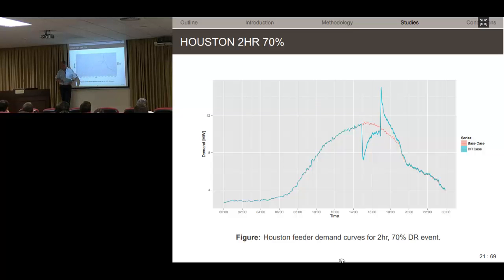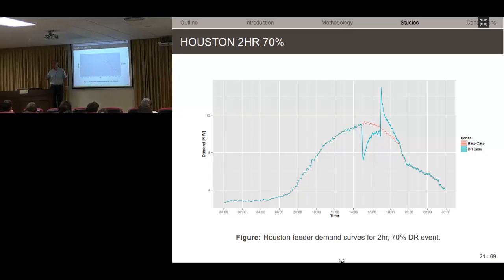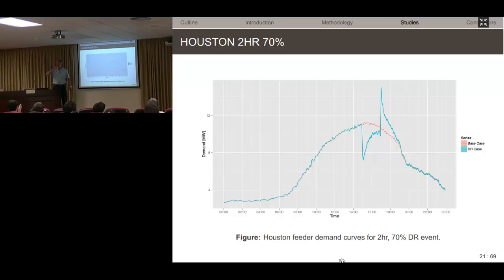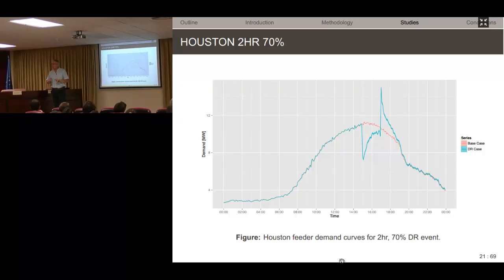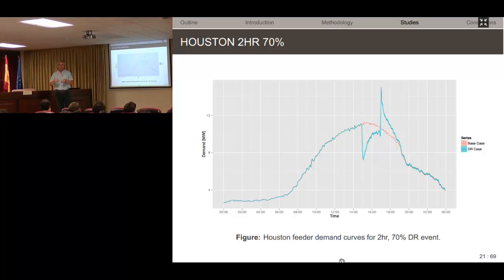How could you deal with this rebound? For example, instead of sending all 1,500 homes to set point reestablishment at the same time, you stagger it every 5 or 10 minutes. So you could avoid some of this. But this is a common problem in demand response programs: we want to help the utility in times of grid stress, and we do—there's a little bit of help here, but this looks like a big problem to all of us.